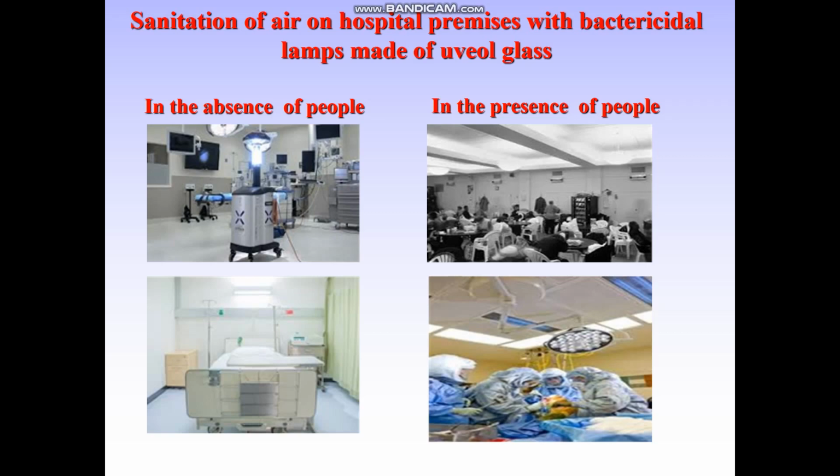Therefore, only the upper portion of the premises is irradiated. Shielded lamps are usually placed evenly all about the room at a height of no less than 2 meters above the floor, in places with the most intensive convection carrying all the air, for example above heating devices, doorways, and window frames. The total duration of the irradiation of air indoors should not exceed 8 hours per day.